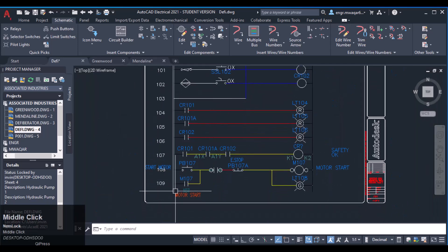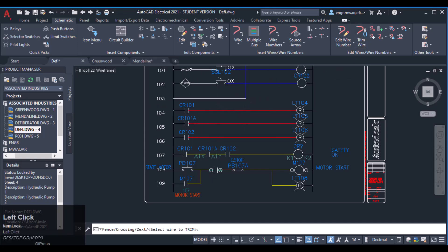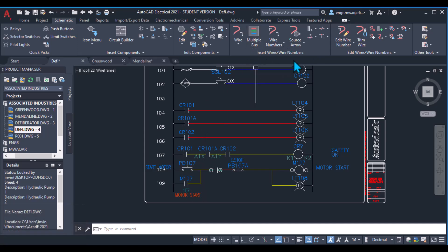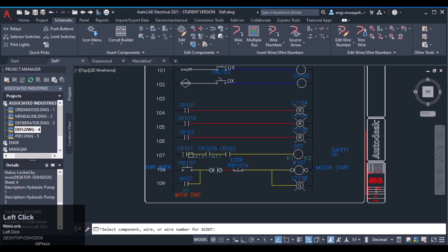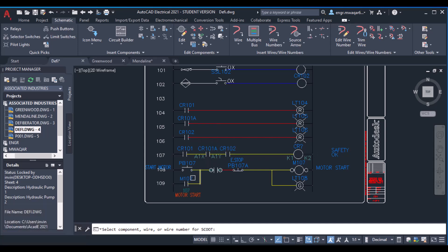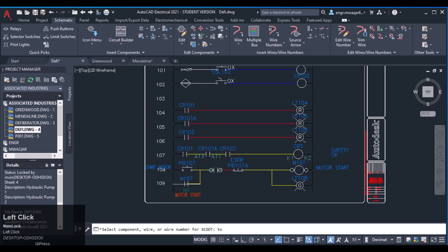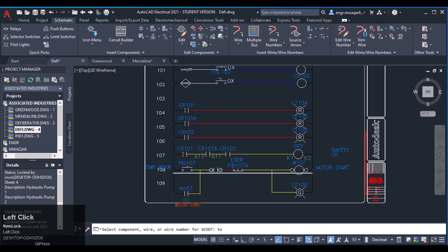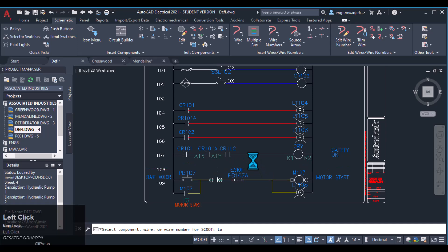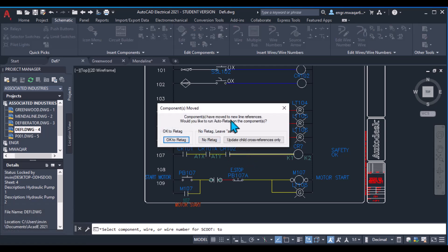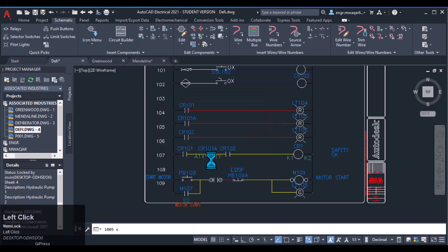Sometimes you need to insert extra rungs between existing rungs. I had inserted a rung between two rungs but there was no gap between them. So I used the Scoot command to move the rungs downward to create space. The whole rung is selected and moved. An important option to note is the prompt: 'Components have moved to new line references — would you like to run auto re-tag on the components?' Click OK to re-tag.